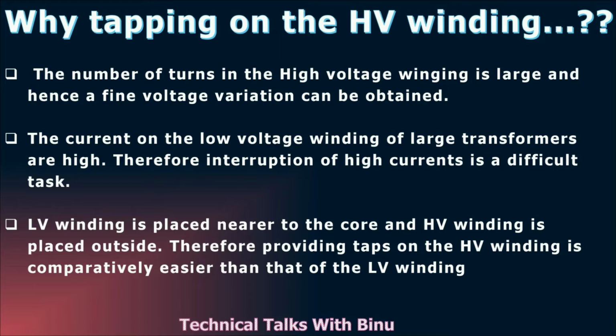The second thing is that if you are putting a tap changer on the LV winding, the volume of the current flowing in the LV winding will be very large and so the interruption of the current will be very difficult. And comparatively, if you are putting the tap changer on the HV winding, then it will be very much easier. The third point is related to the construction feature of the transformer. As the LV windings are placed near to the core and HV windings are placed over that, we will be able to take the tapping easily from the HV windings.